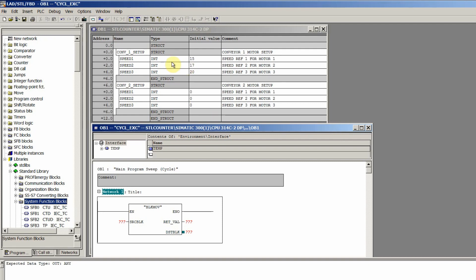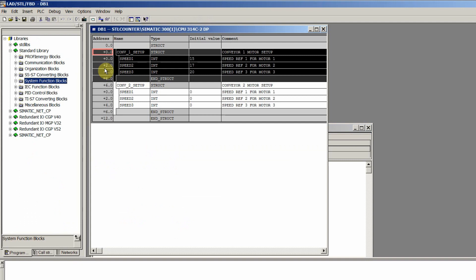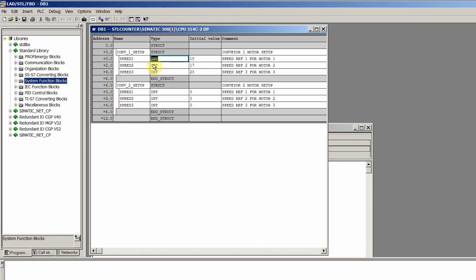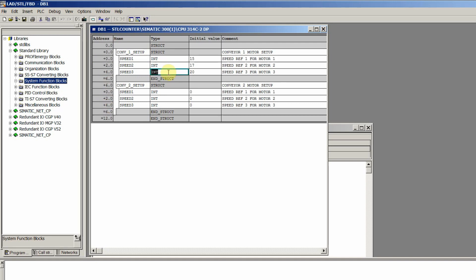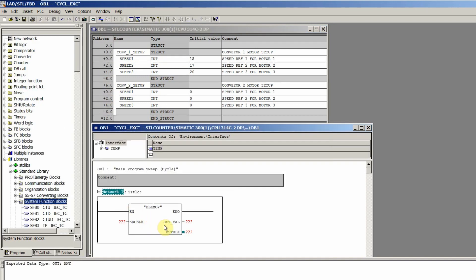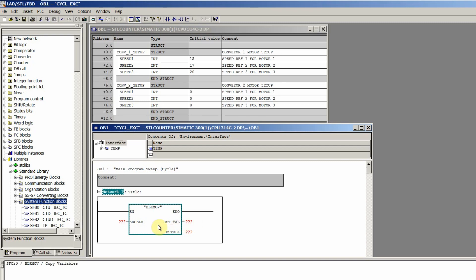One critical thing to note: if you want to copy from one structure to another, the data type must be the same — if it is not the same it will not copy. The name doesn't matter; it will just copy the number of bytes. The return value is used to show any error in the operation. If the data is moved correctly and successfully it will show zero; if an error occurred while copying data from source to destination it will show a non-zero value, which can be checked in the help menu.